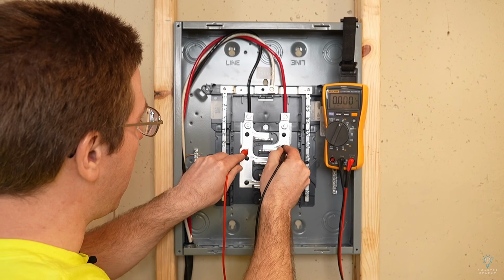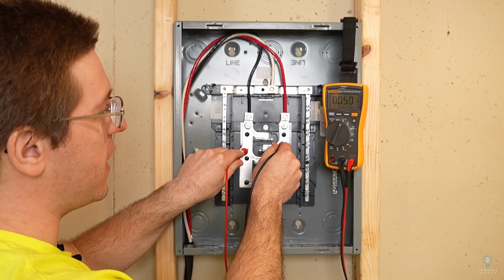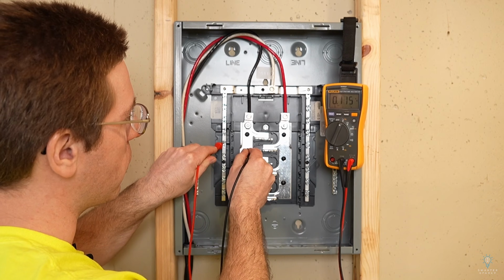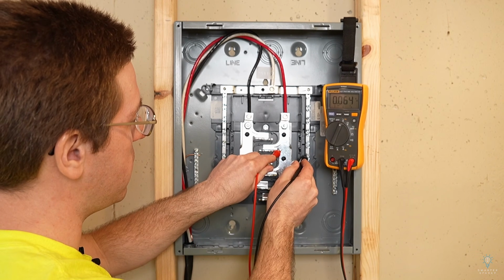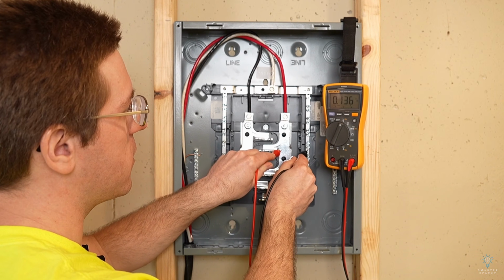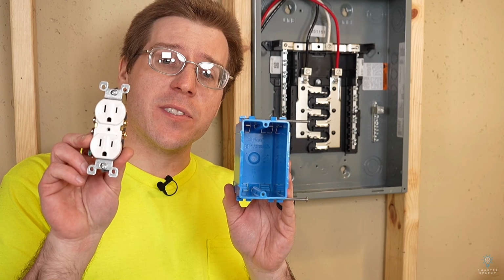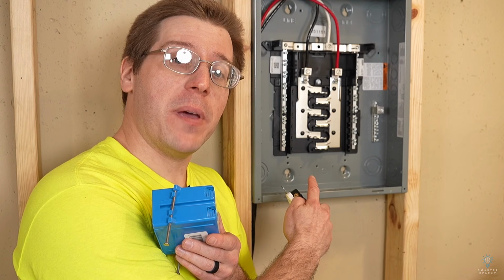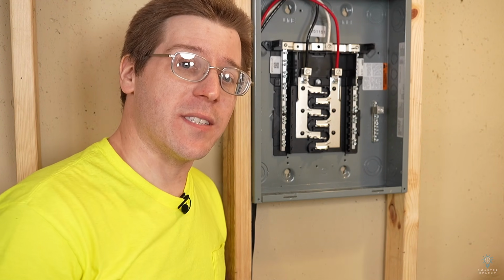And let's just verify this panel is dead. Phase to phase, 0 volts. Phase to neutral, 0 volts. Other phase to neutral, 0 volts. This panel is dead. Real quick, I'm going to install a receptacle out of this sub panel just so we can see how the wires inside land.